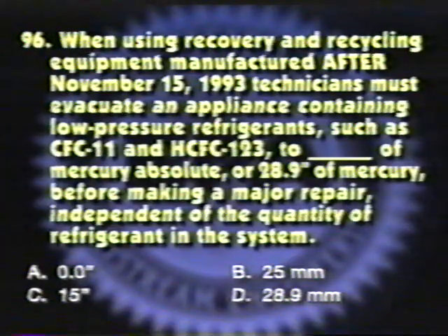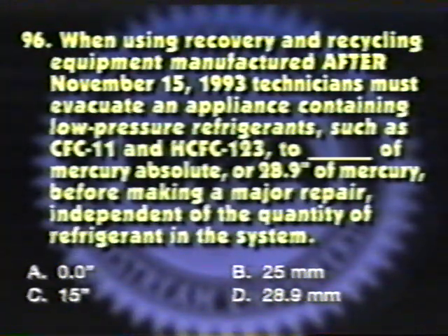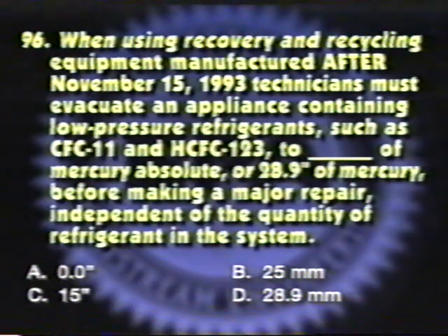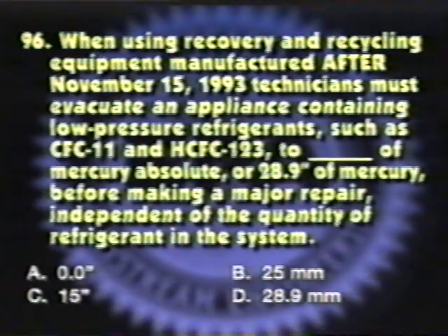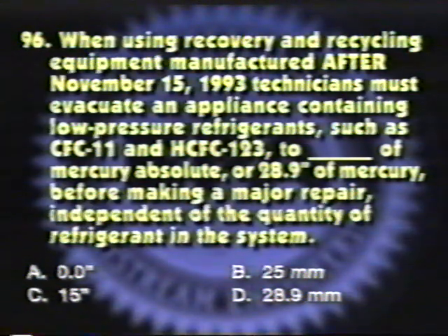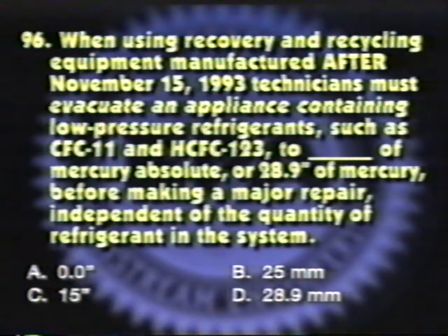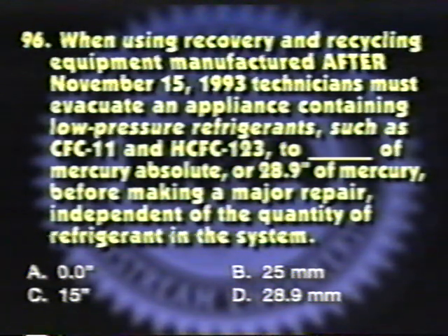When using recovery and recycling equipment manufactured after November 15, 1993, technicians must evacuate an appliance containing low-pressure refrigerants such as CFC-11 and HCFC-123 to what level of mercury absolute, or 28.9 inches of mercury, before making a major repair, independent of the quantity of refrigerant in the system.